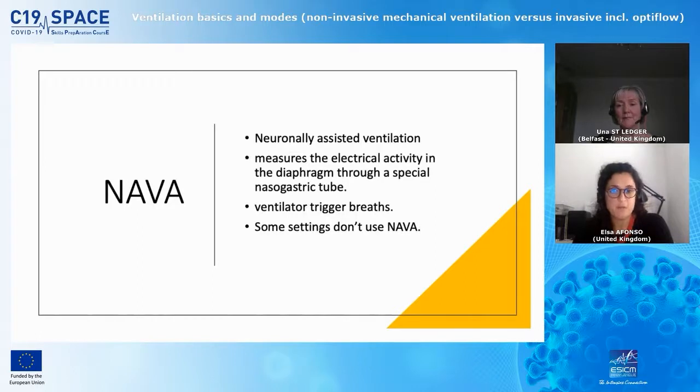NAVA is a mode that is not used in all settings, and it stands for neurally adjusted ventilatory assist. In this mode, the ventilator measures the electrical activity in the diaphragm through a special nasogastric tube. This measurement is then transferred to the ventilator to trigger ventilation.